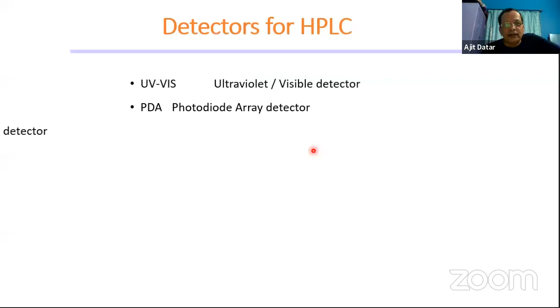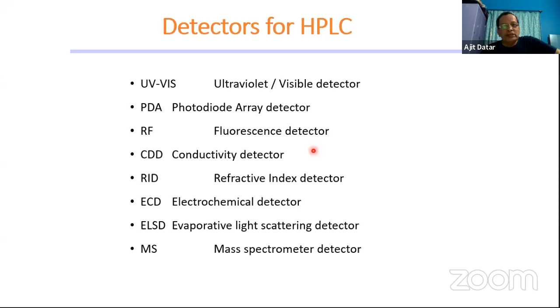Okay. There are several detectors in HPLC. We are not going to talk about each one of them because of the time, but I will show you some of the separations that occurred on these detectors, because these are specific detectors. The UV detector is a very common detector in HPLC, but the condition is that the compound should have a chromophore, it should absorb either ultraviolet or visible radiation. So this is a separation of amino acids, which do not absorb directly, so they have been derivatized. Then I have done the separation of amino acids on a column, using a UV detector.